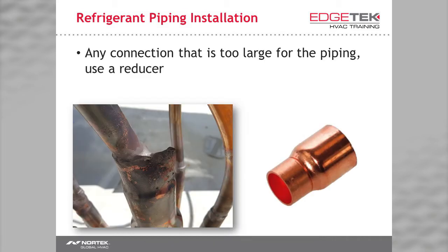Sometimes you may find that your piping is smaller than your Y branches or brazed connections. First, please check that you have the right size. Second, use a reducer if it is the right size. We have all of these piping rules to ensure proper refrigerant flow and oil return. Don't force all of that effort to go to waste with 5 minutes of laziness.